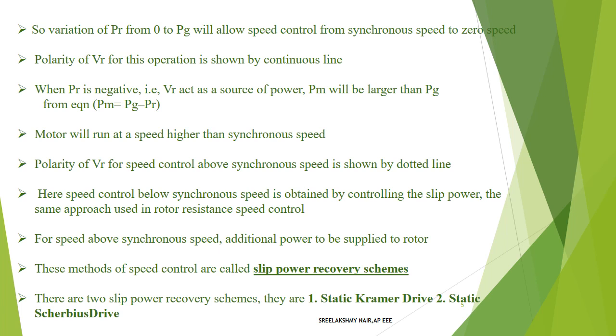The variation of PR from zero to PG allows speed control from synchronous speed down to zero. Speed is below the synchronous speed in this operating range. At that time, the polarity of VR is shown by a continuous line in the diagram. That continuous line represents the polarity of VR for speed control below synchronous speed.